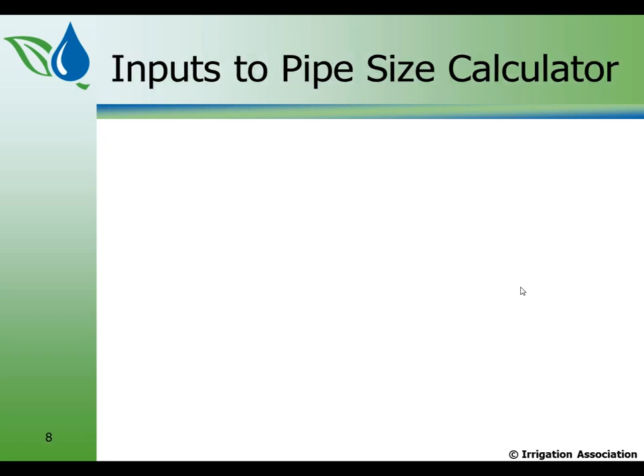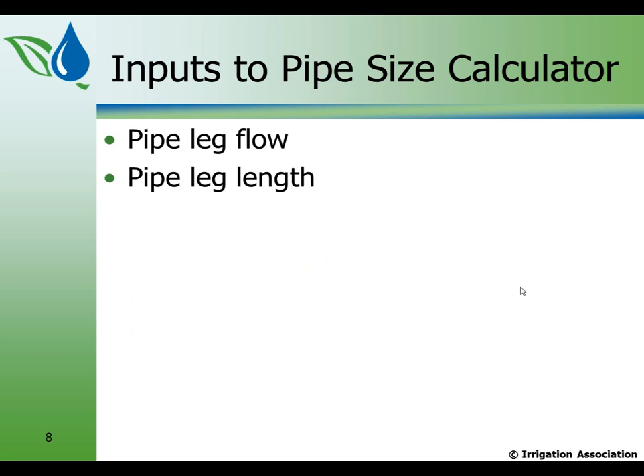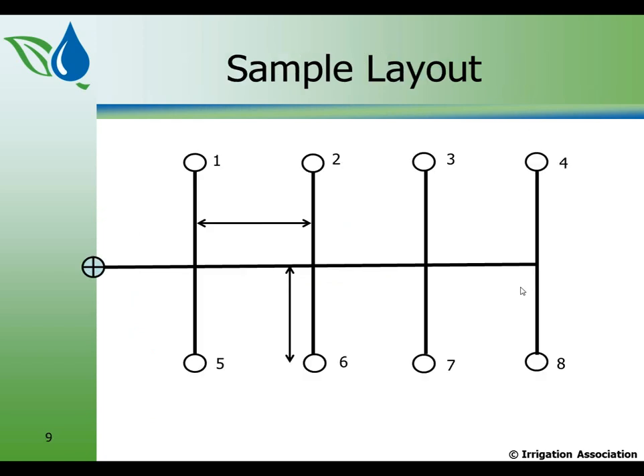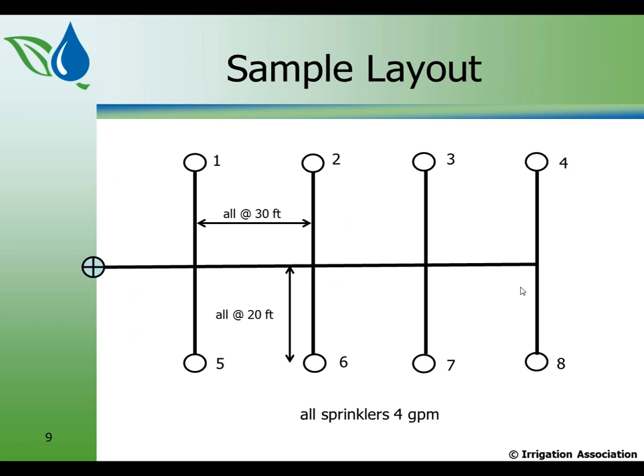What do we need for inputs to the size calculator? First of all, we need the flow in each leg of the pipe, the length of the pipe, the length of that leg, the type of pipe, the materials being used. And here is a sample layout. Now you might look at this as I give you some dimensions and say, well, that's an odd layout. Well, this is done for pipe design reasons, not for good sprinkler layout, so don't be critical of that. We're using throughout this that all of the sublaterals are 30 feet apart, and each sprinkler is 20 feet from the main lateral. So that allows us to get the dimensions.